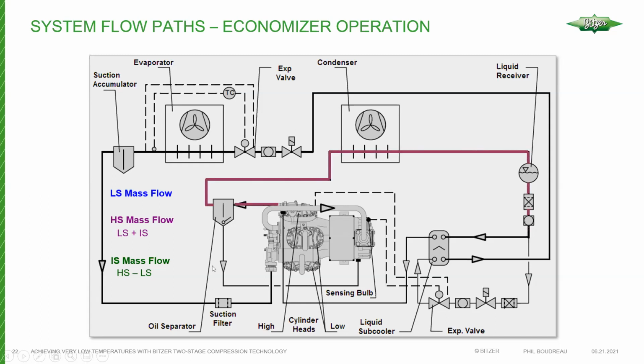So we start out with this purple line here, which is your high stage. Refrigerant leaves the discharge, travels into an oil separator. Generally, you're going to have an oil separator in low temp systems like this because oil travel becomes very complicated when you get into lower temperatures. So you want to generally use a good quality, high efficiency oil separator to limit the amount of oil travel out into your refrigeration circuit. Refrigerant then travels to the condenser where we desuperheat, condense, and then subcool.